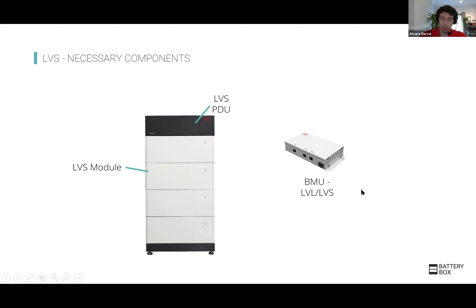But then each tower will have a power distribution unit. This is where the protections are and where this acts as a combiner box internally for the 4 modules. You can parallel in towers of 4 modules each. There is just one exception. In the case that you just have one tower, that one tower could have up to 6 modules.